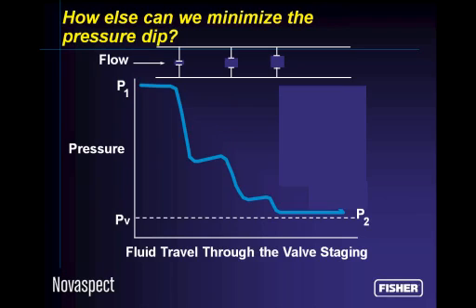Why don't we do a little thought experiment? How else could we minimize this pressure dip such that it didn't drop below the vapor pressure? I've shown you the vapor pressure down here. If I had a single valve, this valve would have a tendency to start up here at my inlet pressure and drop way down, drop below the vapor pressure, and recover above the vapor pressure to P2. I would have a cavitating valve.